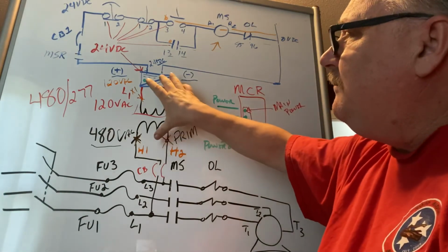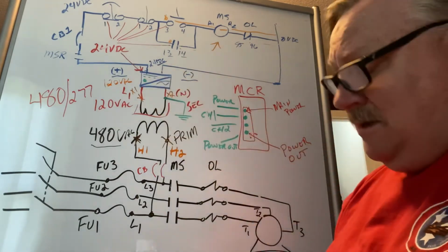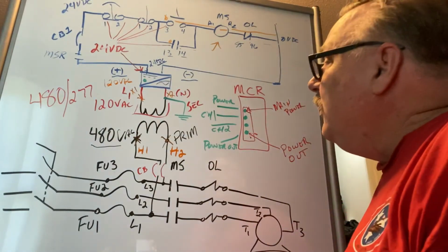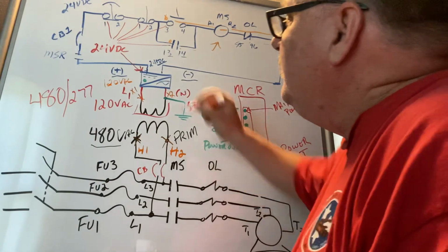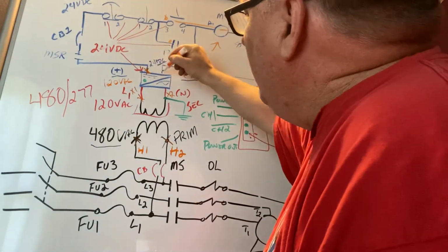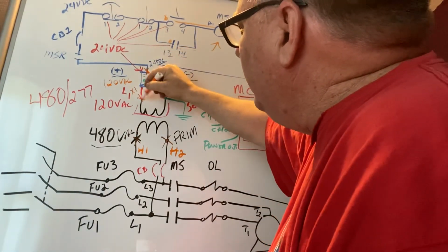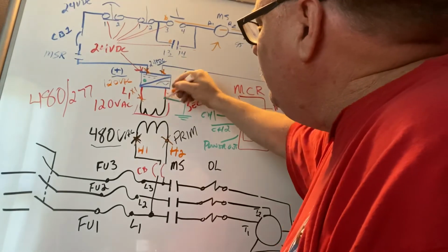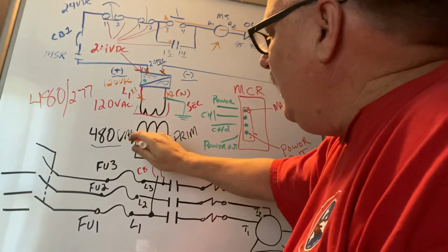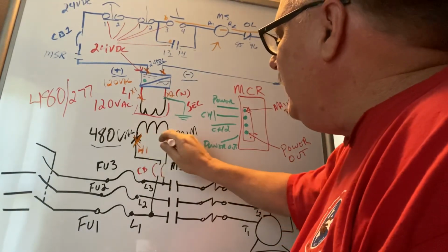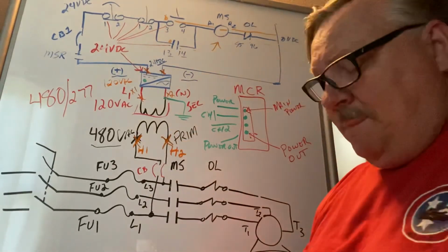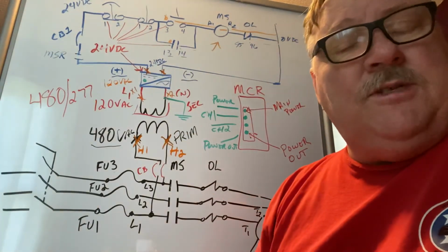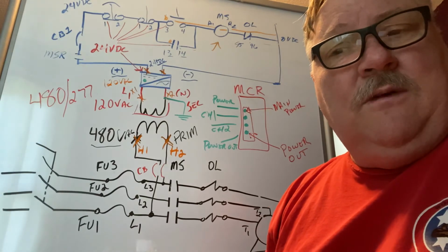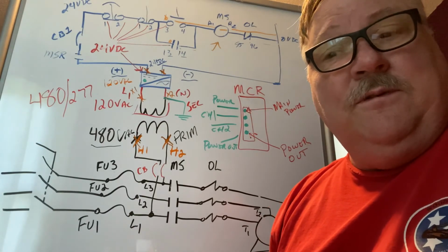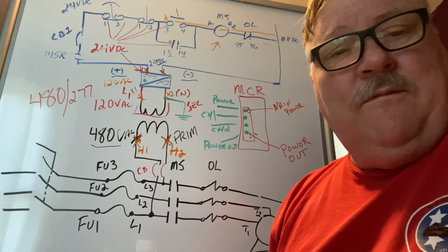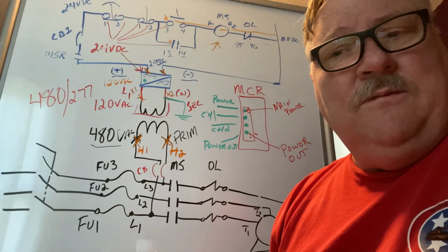So that's where you should see your voltage when you check it. You should see 24 volts going from here to here. You should see 120 volts going X1 to X2. You should see 480 going from H1 to H2. Okay. If you don't have those, check your overload protection, whether it be a circuit breaker or a fuse. And if those are good, you more than likely have a bad device and need to replace it.